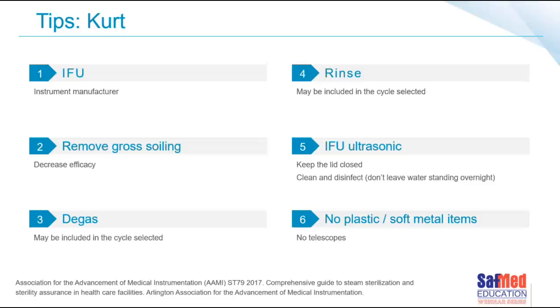Okay. So teach me a bit more about the degassing cycle. How does that work? Degassing. Once again, with the various types of ultrasonic cleaners, as you mentioned, there's fully automated. Some of them have a degas phase in the cycle, and that degas phase is there to remove excess gas from the water. There's always gas in the water, and to ensure the cleaning process, with these tiny bubbles you mentioned earlier, and getting the cavitation correct in the ultrasonic cleaner, we need to do a degas cycle. So remove excess gas from the water.